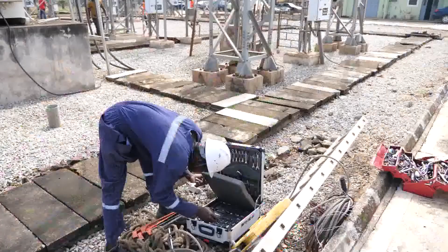And you discover that this power transformer is incorporated with a diverter switch. And the bulk of our maintenance is carried out through the diverter switch, because we have oil immersed in that diverter switch. So if sometimes you don't remove the black carbon deposit, anything carbon is conductive, and by the time you allow it to accumulate so much, instead of serving as an insulator, it will turn into a conductive part, and that will cause serious explosion within the diverter switch, and that will invariably mean the transformer will pack up.